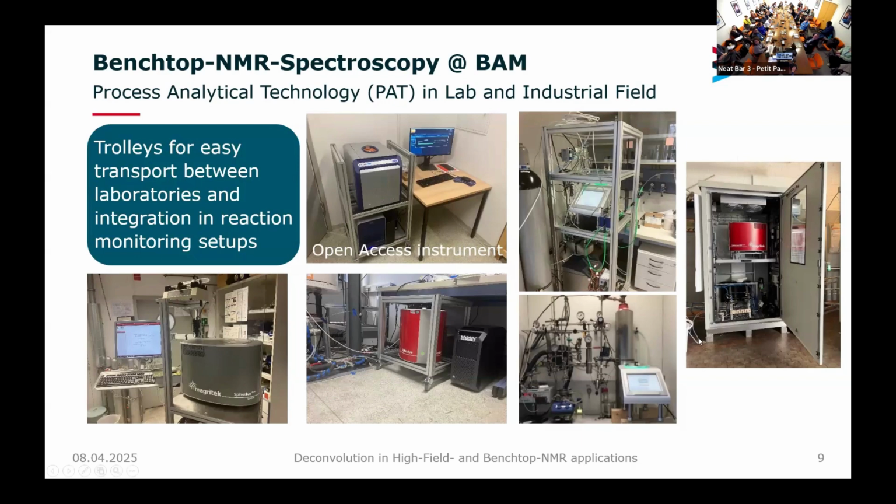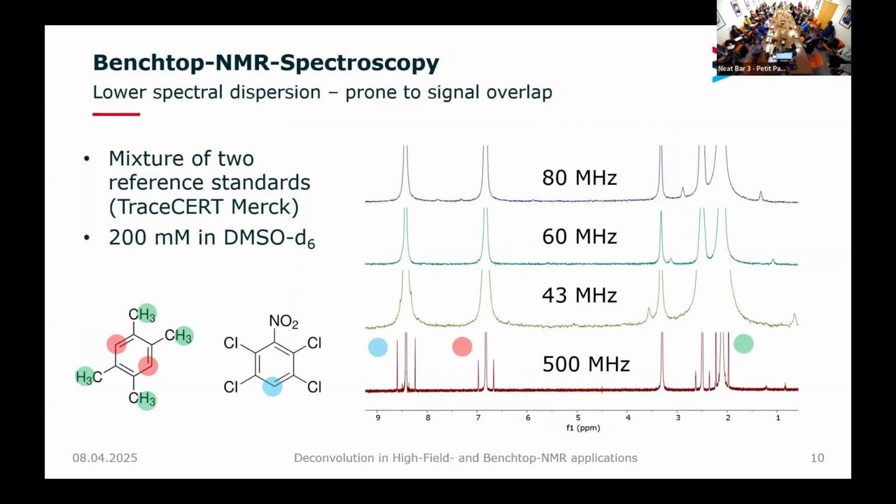And this is an option, something we developed together with an industrial partner, to even bring this into an industrial environment, taking care of explosion safety, with fully automated runtime, so no one is looking at the spectrum anymore and it just reports numbers to the plant's operating staff to control the process. For this, of course, we need a decent amount of automation that we can trust, and therefore we use different approaches for these broader signals.